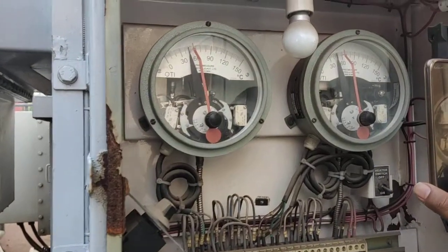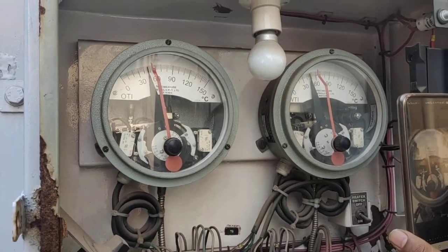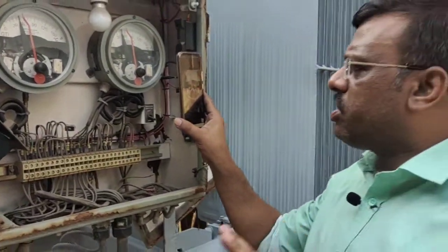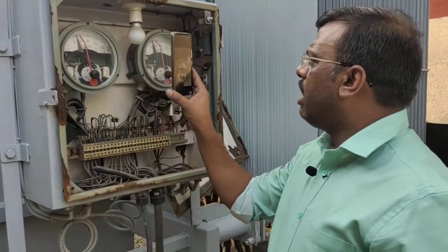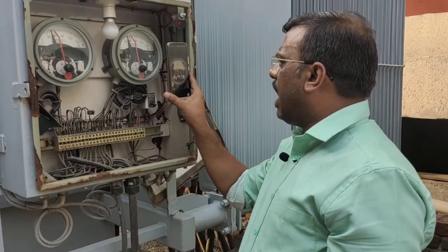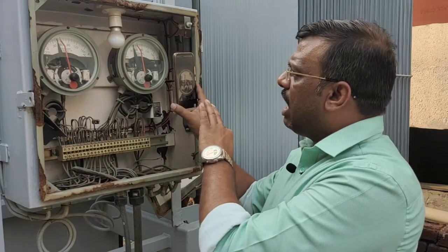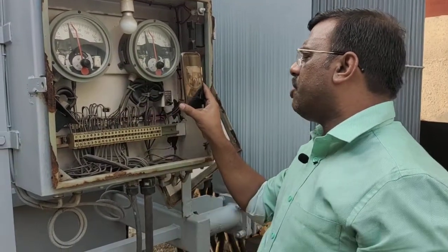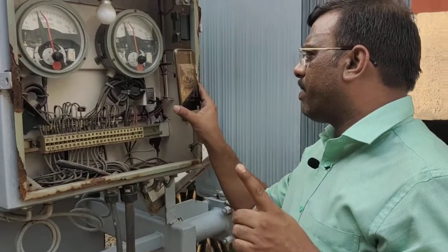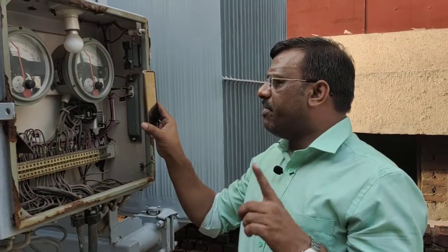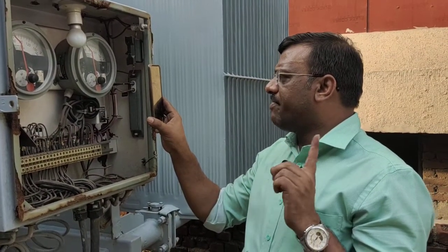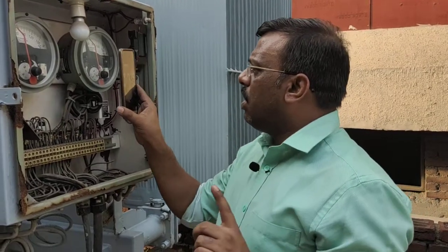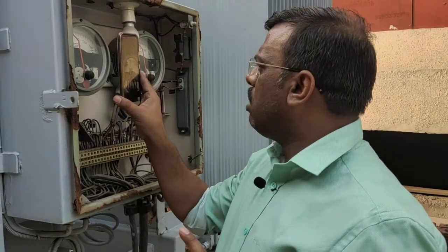That is clear. So that is OTI, the oil temperature indicator, that is WTI, the winding temperature indicator. Okay, so there are the three safeties you have seen: Buchholz relay, OTI, WTI, and all these three safeties are directly interacting with your VCB, with your service VCB or SF6. Clear है यहाँ पे?